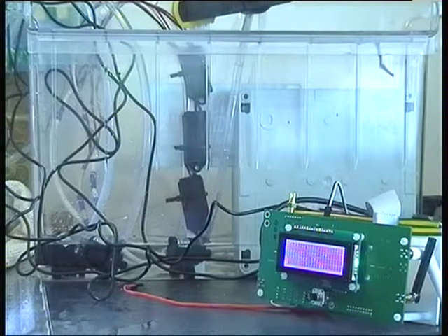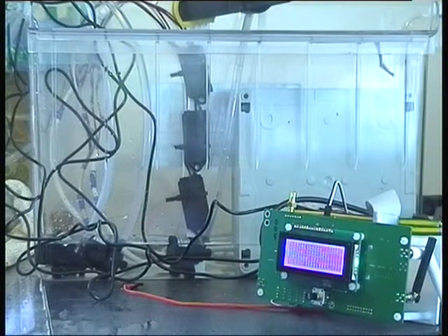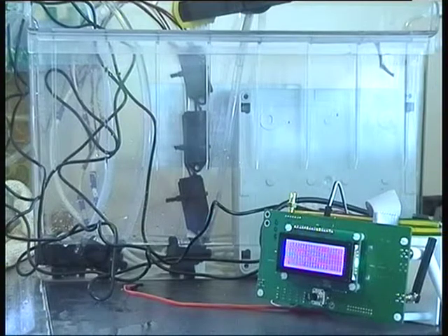In normal operation, only the lower sensor and lower pump operates. When the lower sensor is activated, it will switch on the pump, which will lower the water level in the tank. If for some reason the lower sensor fails, or the lower pump fails, the middle sensor will be activated and switch on the middle pump. If for some reason that fails, the top sensor will activate and will switch on the top pump.